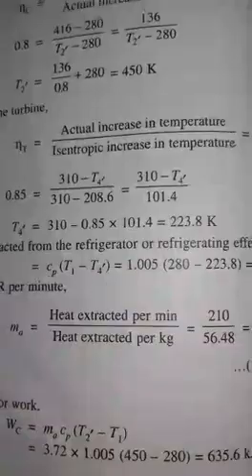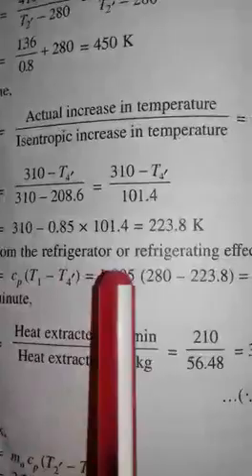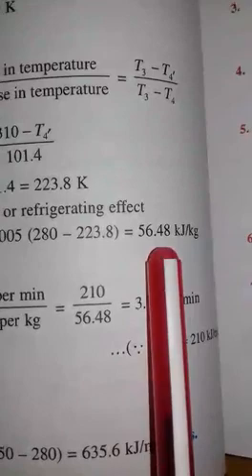The refrigerating effect is given by Cp × (T1 − T4-dash). From the figure, the cooling portion corresponds to T1 minus T4-dash actual. Using the relation, the refrigerating effect = Cp × (T1 − T4-dash) = 1.005 × (280 − 223.8) = 56.48 kJ/kg.